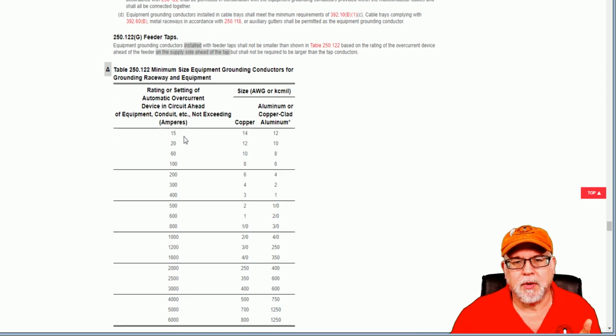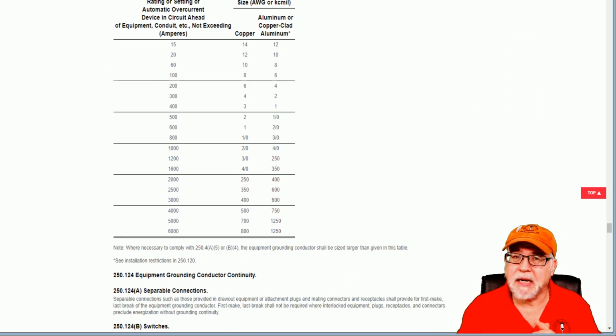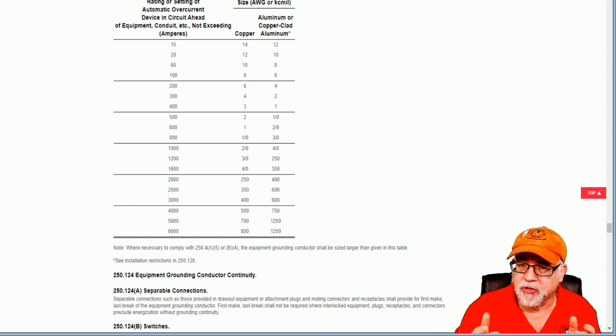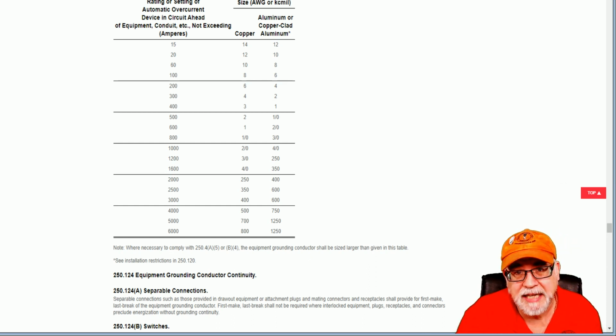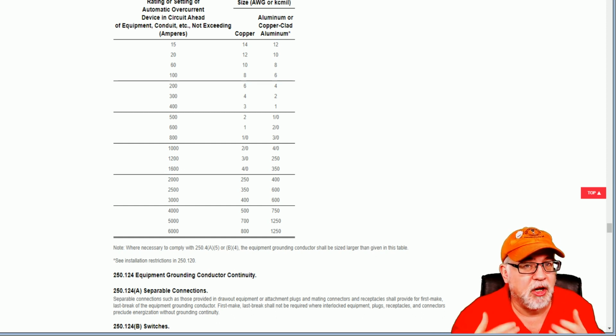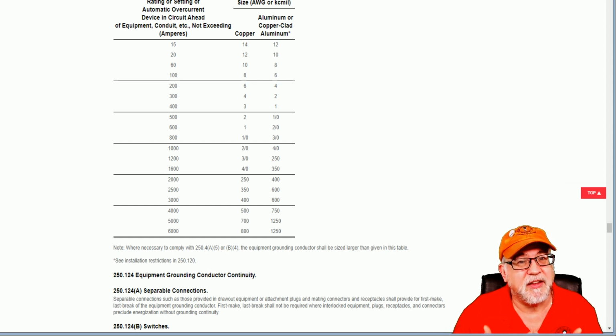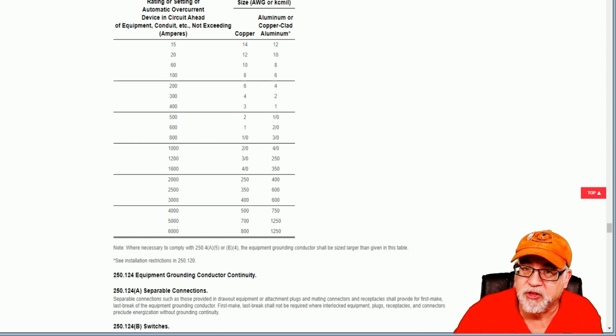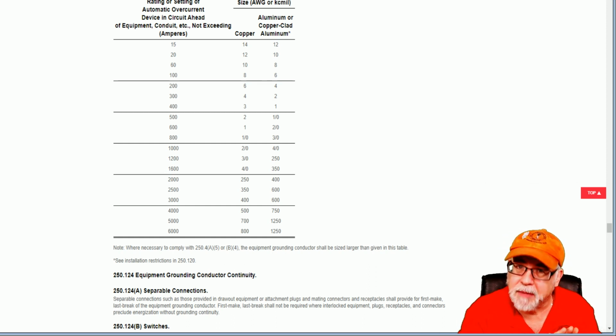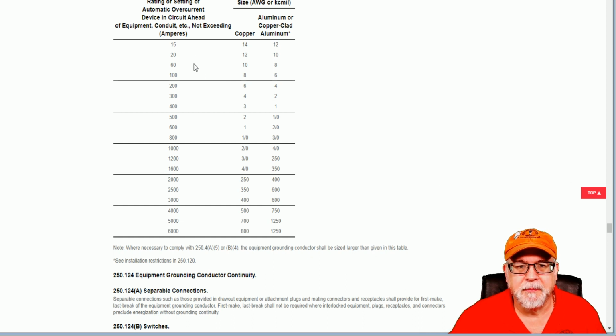But here's what we want to look at. This is the table. This is a minimum size. Now, this is a minimum. Could it be larger? Absolutely. Is it required to be? Absolutely not. But when an engineer increases the size of the ungrounded conductors, thus increasing the size of the equipment grounding conductor, then it's being sized above the minimum, and so it's based on the rules in 250.122(B) for increasing the size. That doesn't change that we start with a minimum value. Now, the reason we want to bring this up is you'll notice that a 40 amp device does not appear here at all. So a lot of people get confused about this table.